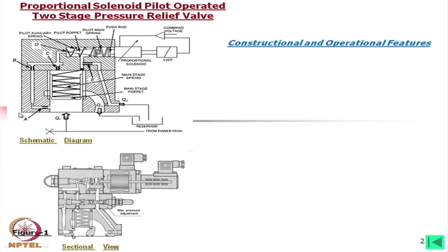This means that whatever pressure is here, the same pressure will be here also. You can see this path, it will be here also, here, everywhere the pressure will be the same, and this will not open. Now, we are operating at a 10 megapascal range, say after 10 megapascal this will open. So, what we can do, we can set this current for 10 megapascal.